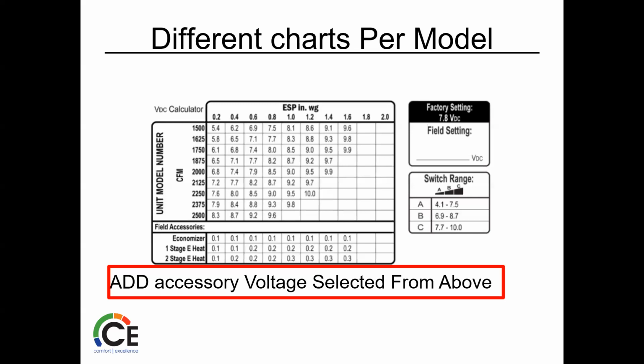Now, again, once you get this set up, you're going to want to check that airflow again, just to make sure that it didn't get way out of whack, or if you have to adjust it. But for the most part, you don't. Question in the test is, can you set this up without knowing the static pressure? The answer is absolutely not. I mean, you could turn that dial all day, but you're never going to know what your airflow is unless you know what your static pressure is. So you may have to do it a couple of times to really dial it in, but you got to know static pressure. You got to have a manometer.